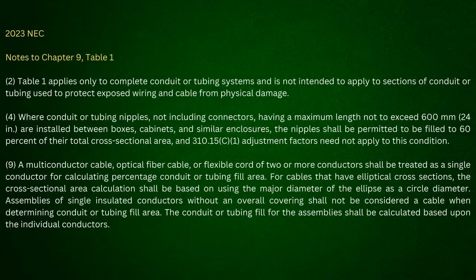So the circuits that were on the interior panel inside the building, we'd relocate out to the outside, and then we'd tag on and make that a complete raceway from our new panel to the old panel, making that our junction box. Mm-hmm. And so I would have to do the conductor fill, because that's a complete raceway on both ends. Okay.